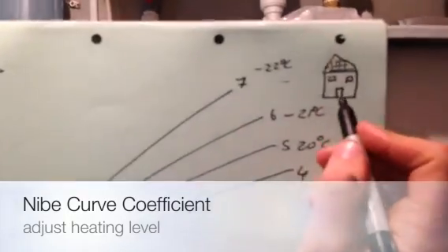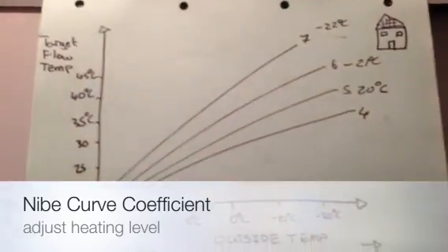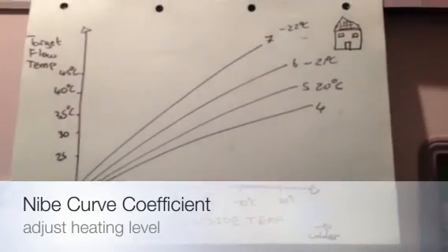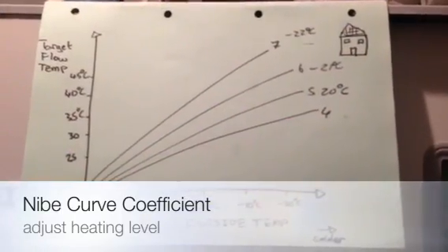But this depends greatly on the insulation and the type of house you have. If you have a lot of glass, you'll have a lot of heat loss, so you'll need a higher curve. If you have a poorly insulated house, you'll need a higher curve. If you have a well-insulated house, you'll need a lower curve.